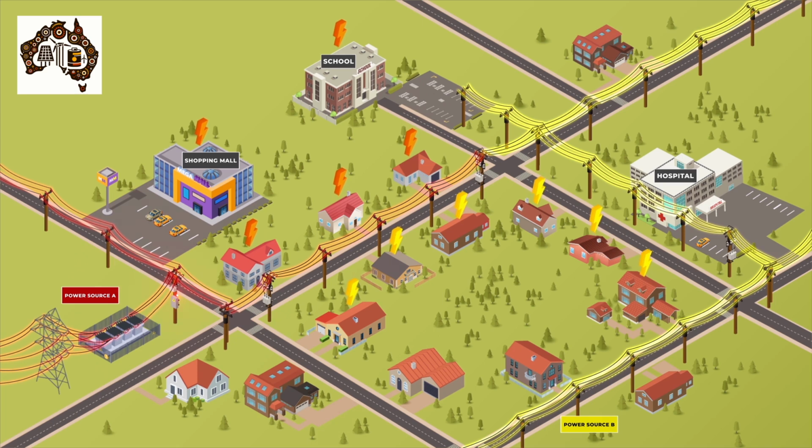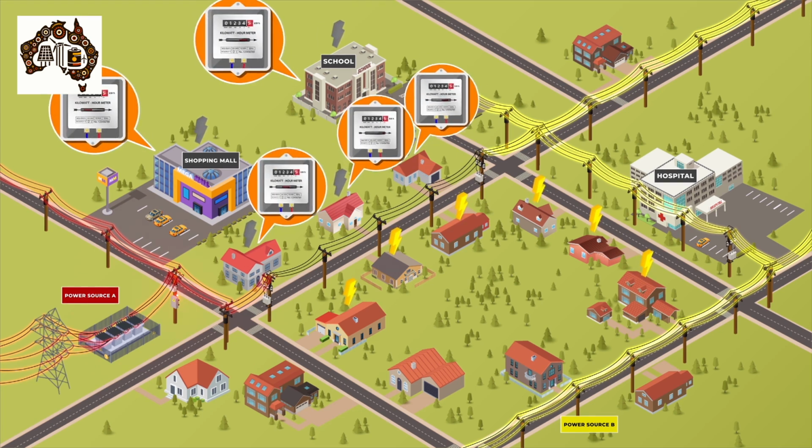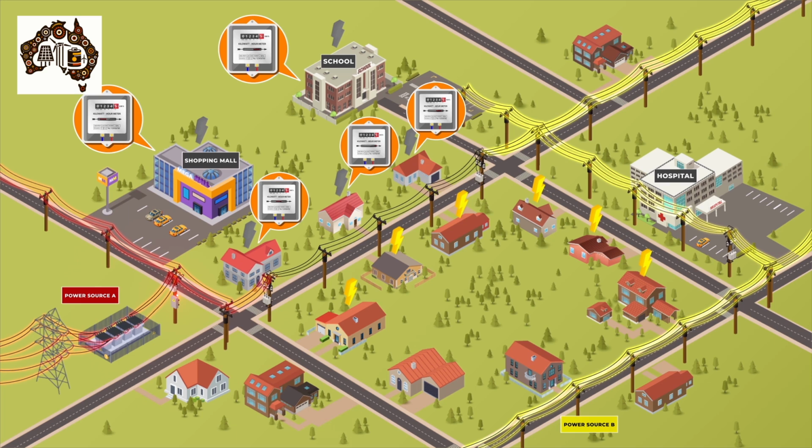In this scenario, the dropout fuse, being a non-telemetered network protection device, has blown, resulting in an unplanned outage. The distribution network service provider remains unaware of this outage due to the lack of visibility into this specific power disruption. This lack of awareness is exacerbated by the absence of advanced metering infrastructure, smart meters. As a result, the DNSP relies on customers to report power outages.